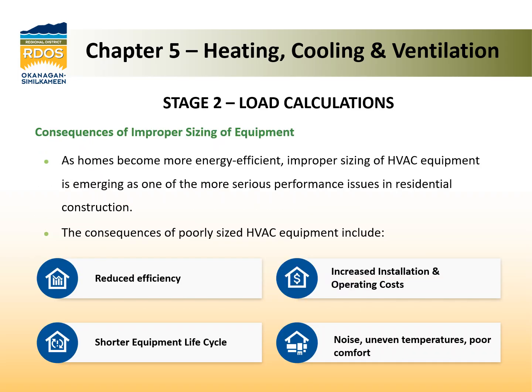One of the most common problems we see when something is not working well in a relatively new system is the load calculation was not done, which means the equipment is not well matched to the home's actual heat loss and heat gain. It will cause reduced efficiency, typically higher operating maintenance costs, shorter life cycle of the equipment, uneven temperatures, poor comfort and noise. So obviously there's no upside to skipping properly done load calculations.